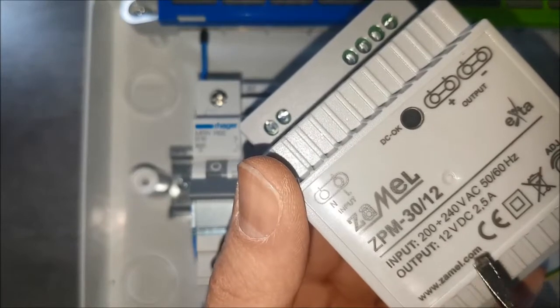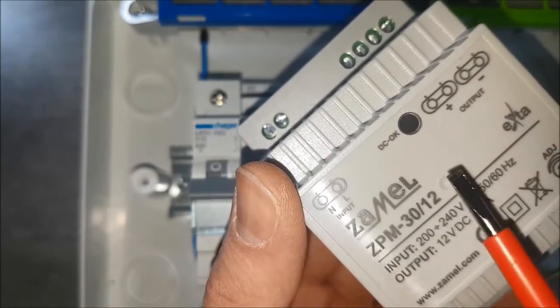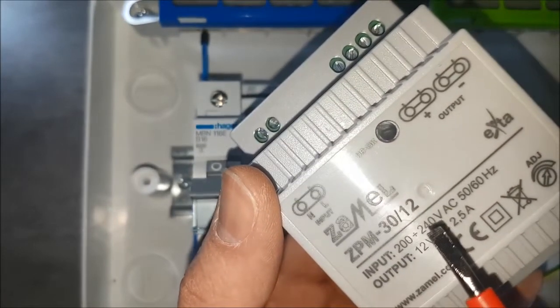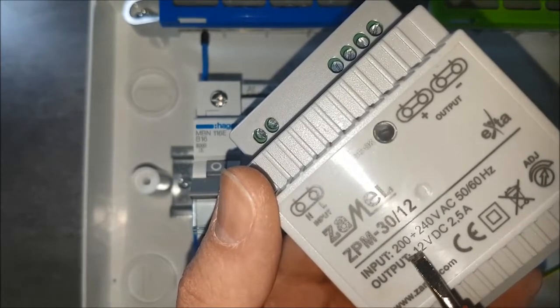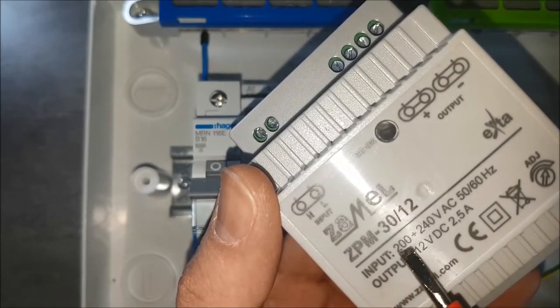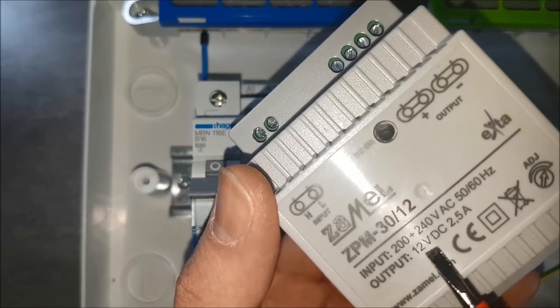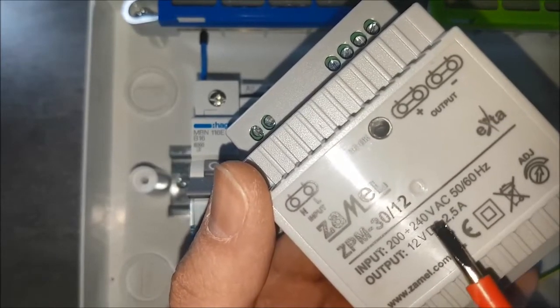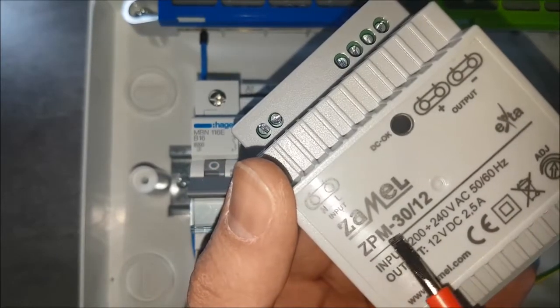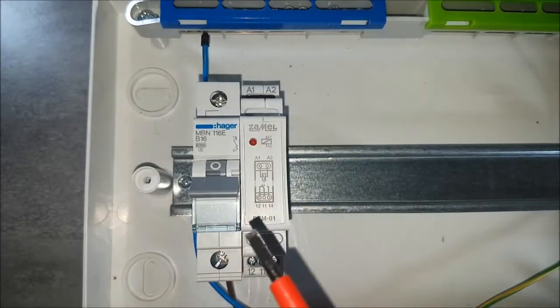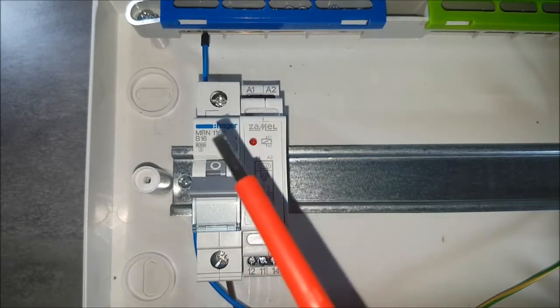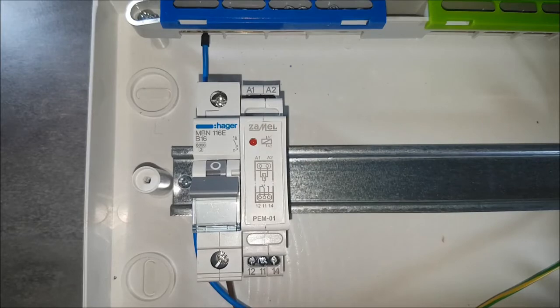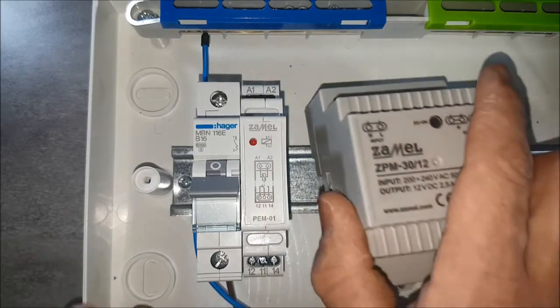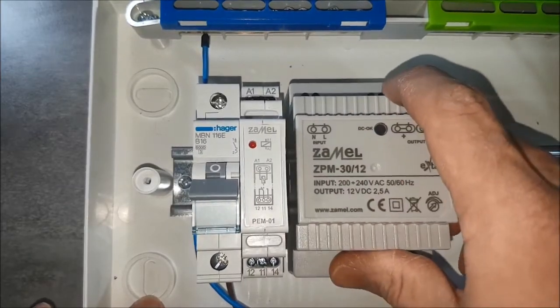PEM-01, 012 relay is powered with 12 volts AC or DC voltage. Therefore it's necessary to install in switchgear the ZPM power supply, for example the ZPM30, 12 model. This device is powered by 230 volts AC and on the output generates voltage at the level of 12 volt. The maximum power connected to the ZPM30, 12 power supply is 30 watt, which allows to generate current at a maximum level of about 2.5 amps.